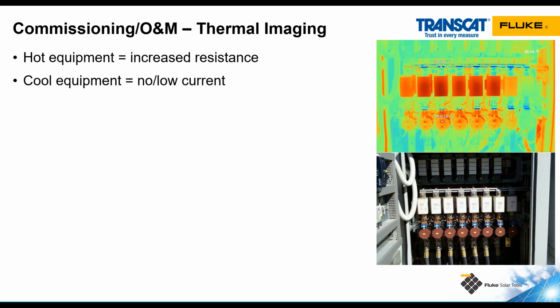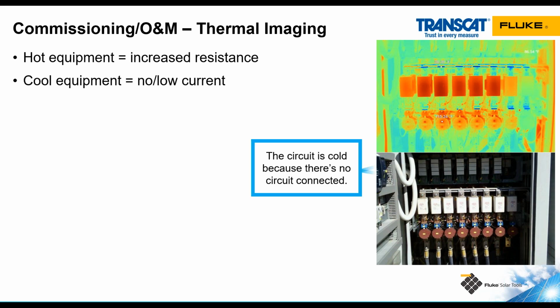When we're doing thermal imaging, we can look for things that are hotter than they should be or hotter than similar components. We can also look for components that are cooler than similar components. In this picture here, we've got several circuits in this box. The one on the right is cooler than all the rest of them. That's because there's no circuit connected to that component. So obviously it's going to be cooler than the rest of the components that are operating.